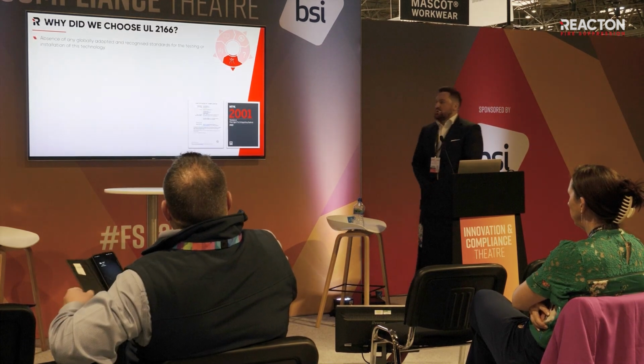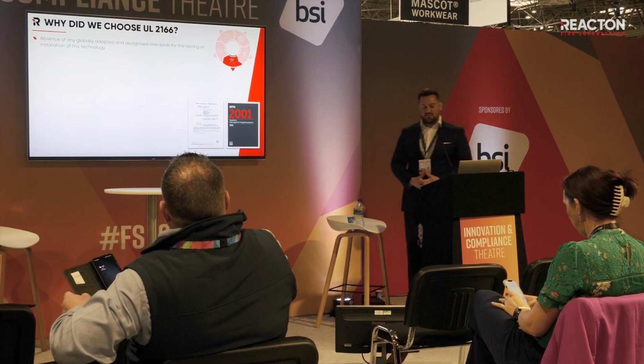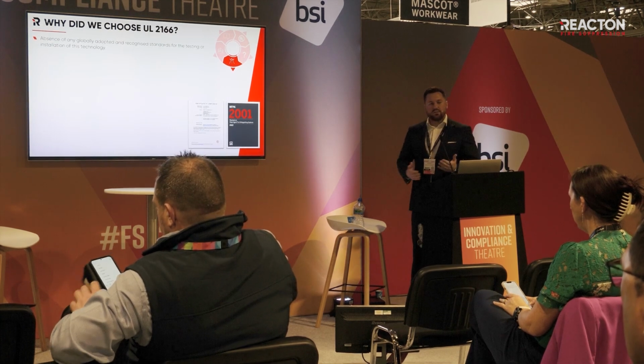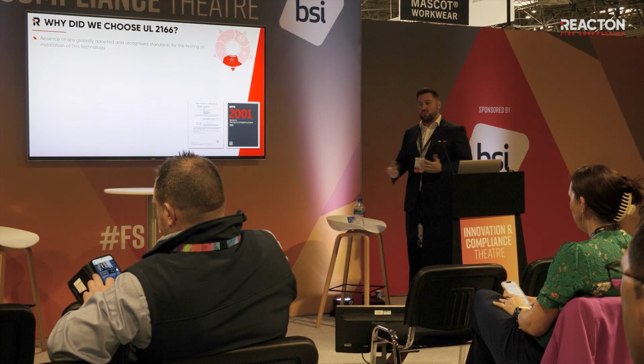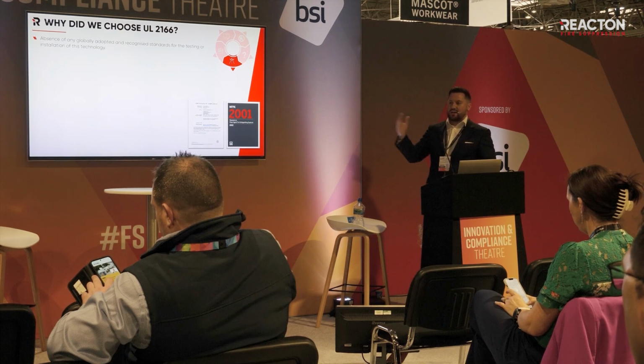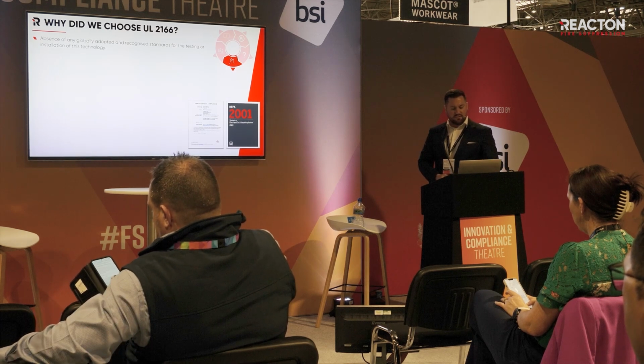Why did we choose this? So everyone understands that there's standards out there for fire extinguishing systems, but there's a big absence of any globally adopted and recognised standards for the testing and installation and design of this technology. So we needed to do that. People who do total flood systems are used to designing a system in accordance with the standards that everyone knows for the total flood systems, such as ISO 14520, BSEN 15004, or NFPA 2001. That doesn't cover this technology. There wasn't a standard that covered it all. So we wanted to use those references to be able to create this standard or product.